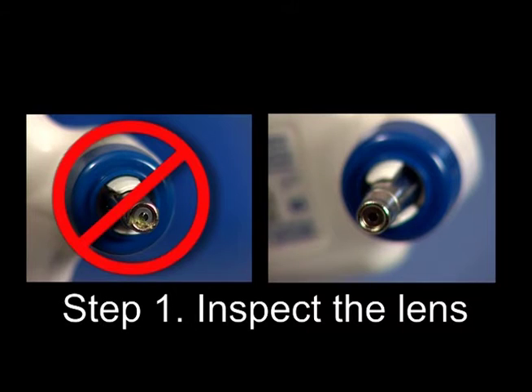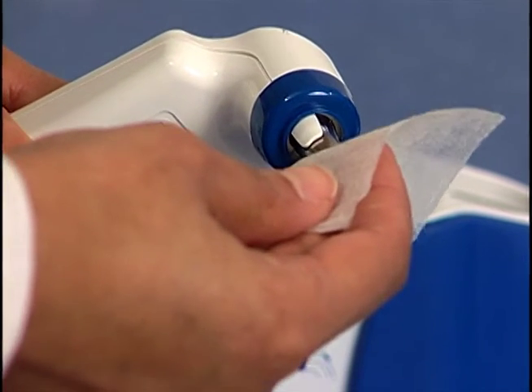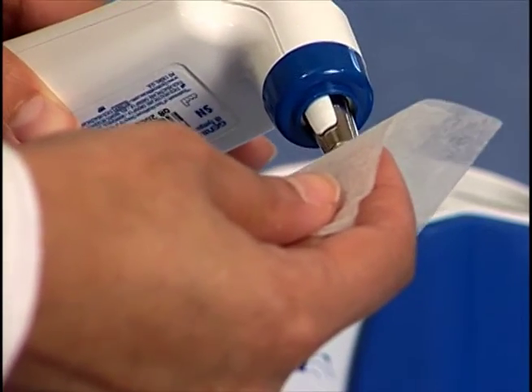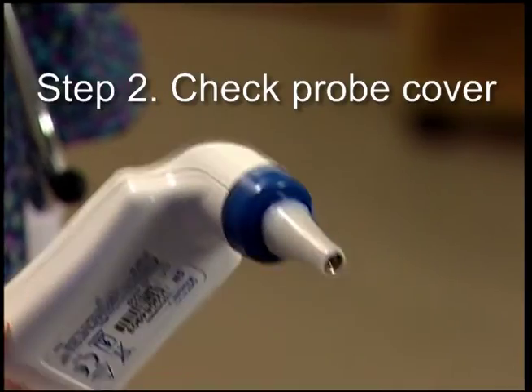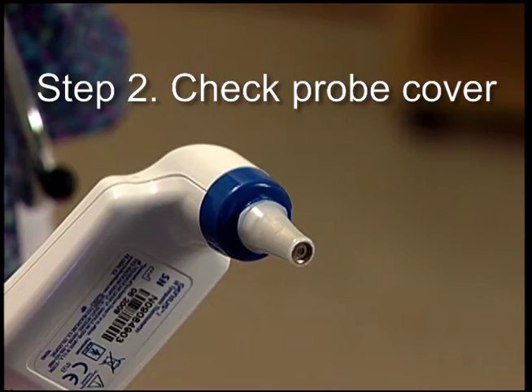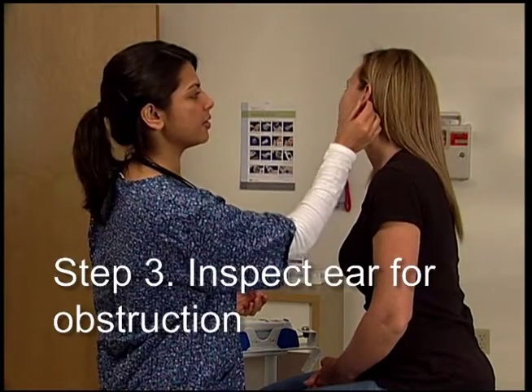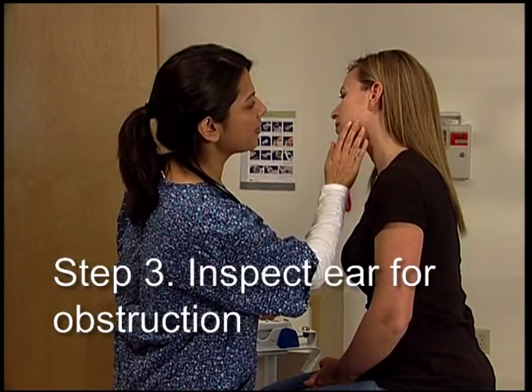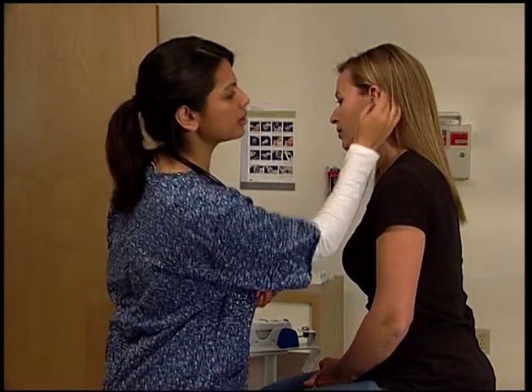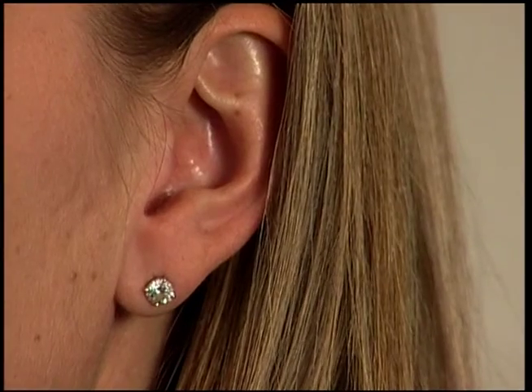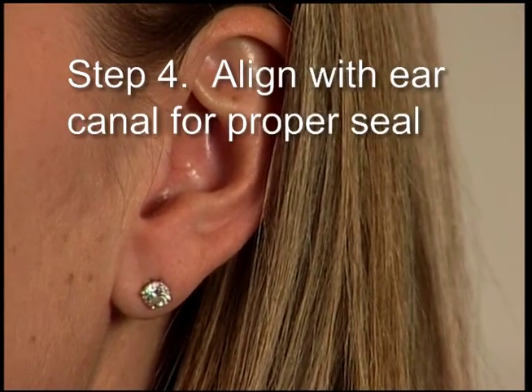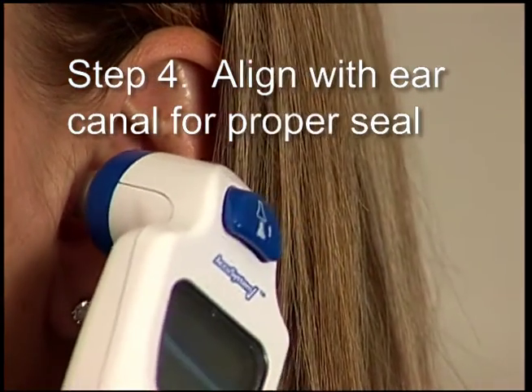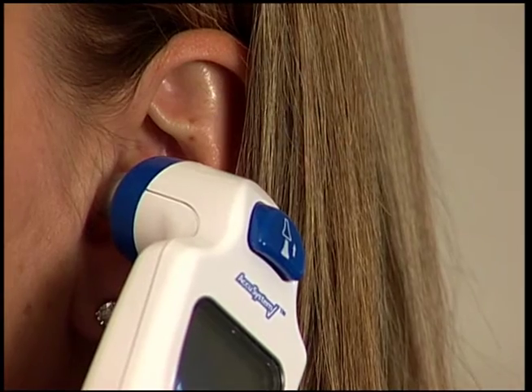If the Genius 2 is providing consistently low or incorrect temperatures, please take the following actions. 1. Inspect the lens. Is the lens perfectly clean? Clean the probe lens if needed with a dry lens wipe, dry lint-free gauze, or dry cotton-tipped applicator. 2. Is the probe cover on properly? 3. Did you inspect the patient's ear for obstructions? Try the other ear if needed. 4. Are you aligning the Genius 2 correctly with the ear canal and getting a good seal? Correcting these problems should assure the delivery of accurate readings.